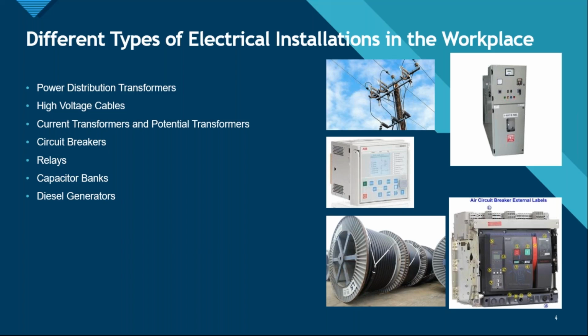Then circuit breakers. I think most of you are familiar with circuit breakers. There can be a huge number of circuit breakers, like you can see here in the rightmost two pictures. The top one is the vacuum circuit breaker panel, and the bottom one is the air circuit breaker panel. There can be different types of circuit breakers depending on the current rating, right? A circuit breaker, as the name suggests, breaks the circuit, right? So whenever a fault is detected by the relay, it can give a command to the circuit breaker, and the circuit breaker will just break the circuit so that no high current passes through the circuits, damaging any equipment that the panel might be connected to, right?